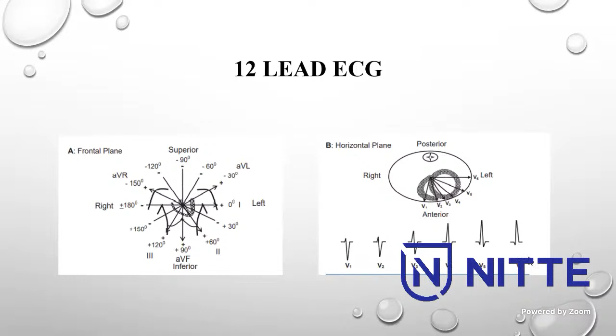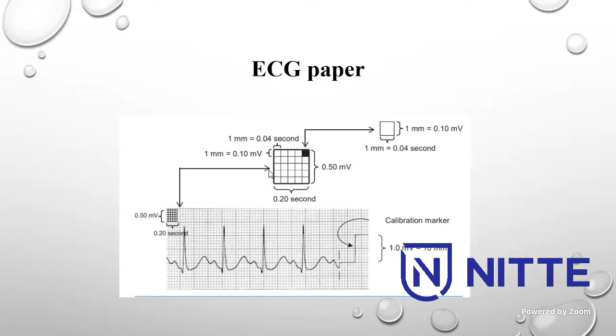Coming to calibration of an ECG paper, this is how an ECG strip looks. The speed of recording is 25 millimeters per second. Along the x-axis you have the time, and along the y-axis you have the amplitude. It is calibrated in such a way that one small square corresponds to 0.04 second on the x-axis, and in height, if you see the amplitude, 1 millimeter is 0.1 millivolts. So this is how a standard ECG paper is calibrated.